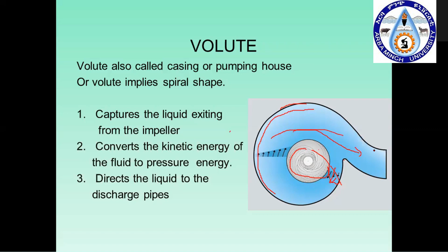You can see what this volute is. The volute has a spiral shape. While the impeller at the center rotates, its use is to draw the liquid and throw the liquid against this volute. You can see the volute shape constantly increasing from the fluid entry towards the fluid exit. Why is this increasing shape needed? It has to convert the kinetic energy imparted to the fluid by the impeller. While this spiral or volute casing continuously increases the area, the kinetic energy of the water is converted into pressure energy, and finally the volute sends the water towards the exit.